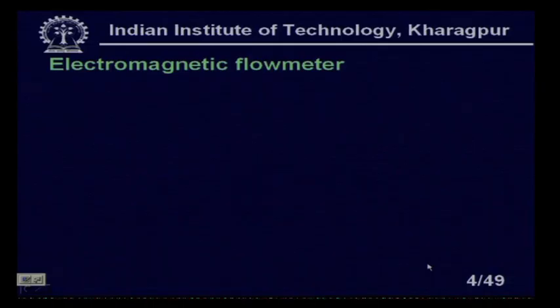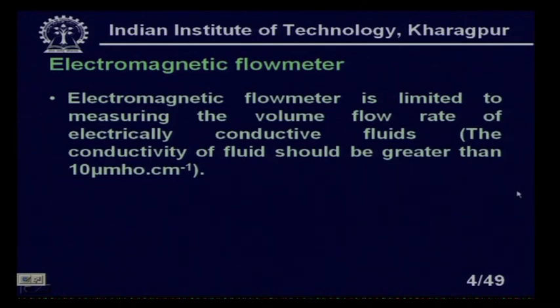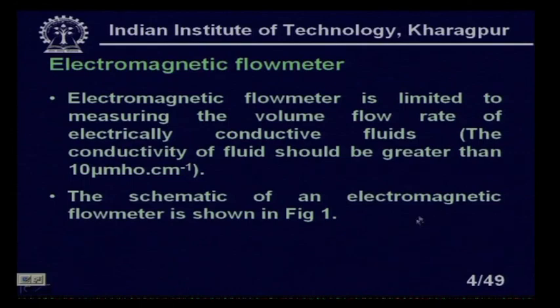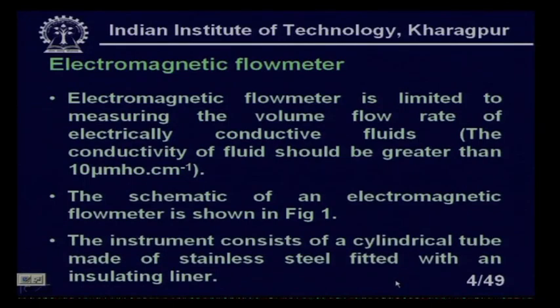Electromagnetic flow meter is limited to measuring the volume flow rate of electrically conductive fluid. The conductivity of the fluid should be greater than 10 micromho per centimeter. If it is less than this, the flow meter will not work. However, there is no higher limit on the conductivity. In some situations, the pipe and electrode installation will be different if the conducting liquid has very high conductivity.